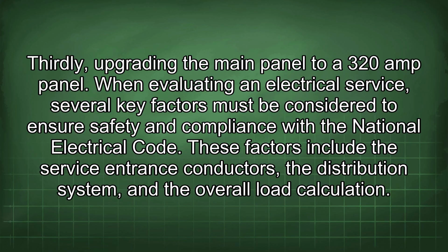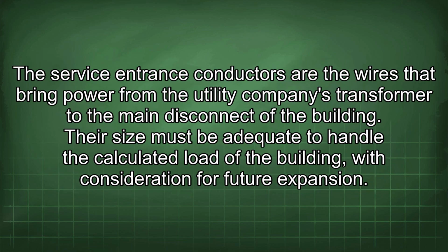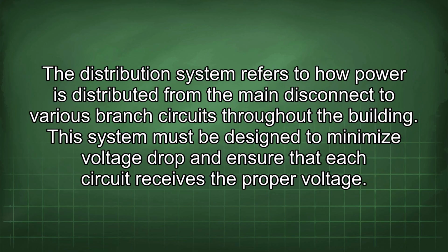When evaluating an electrical service, several key factors must be considered to ensure safety and compliance with the National Electrical Code. These factors include the service entrance conductors, the distribution system, and the overall load calculation. The service entrance conductors are the wires that bring power from the utility company's transformer to the main disconnect of the building. Their size must be adequate to handle the calculated load of the building, with consideration for future expansion. The distribution system refers to how power is distributed from the main disconnect to various branch circuits throughout the building. This system must be designed to minimize voltage drop and ensure that each circuit receives the proper voltage.